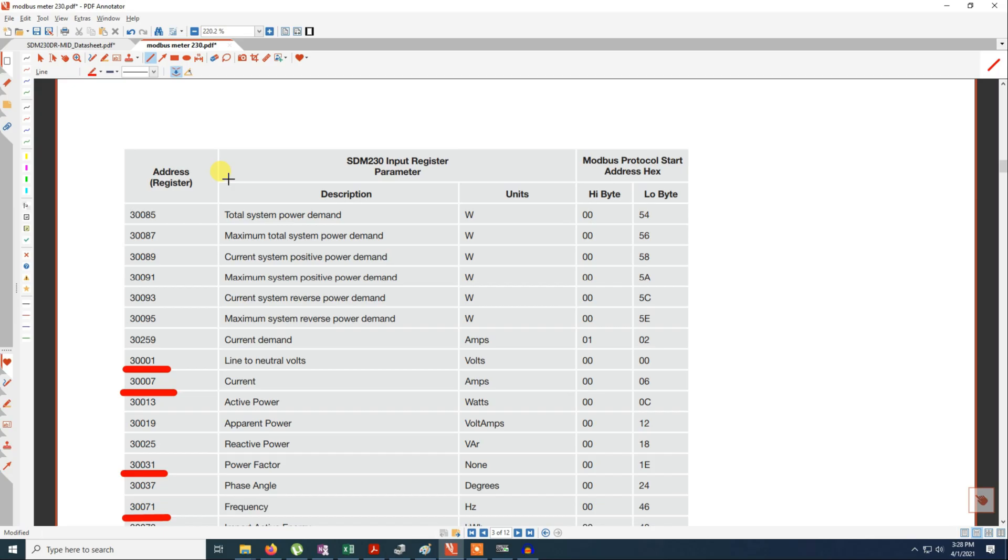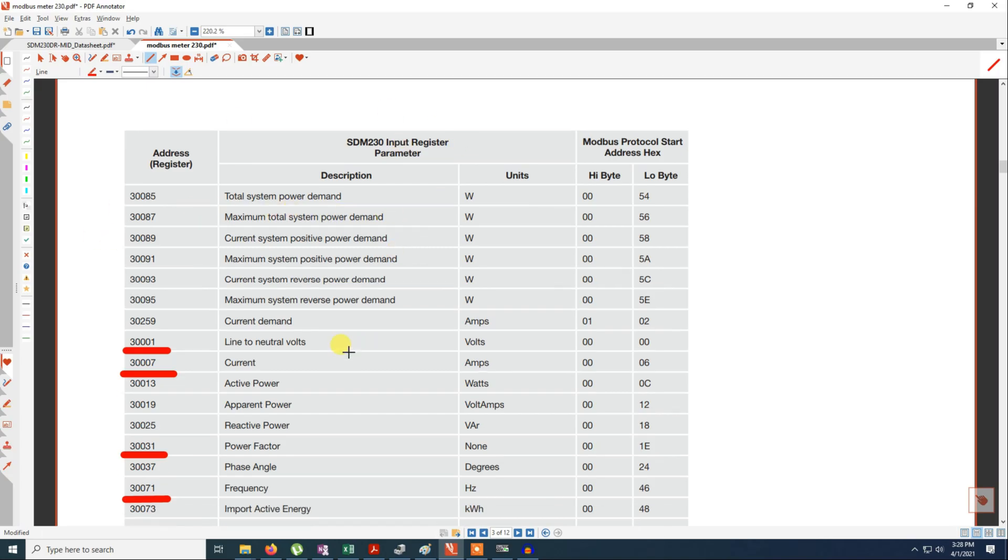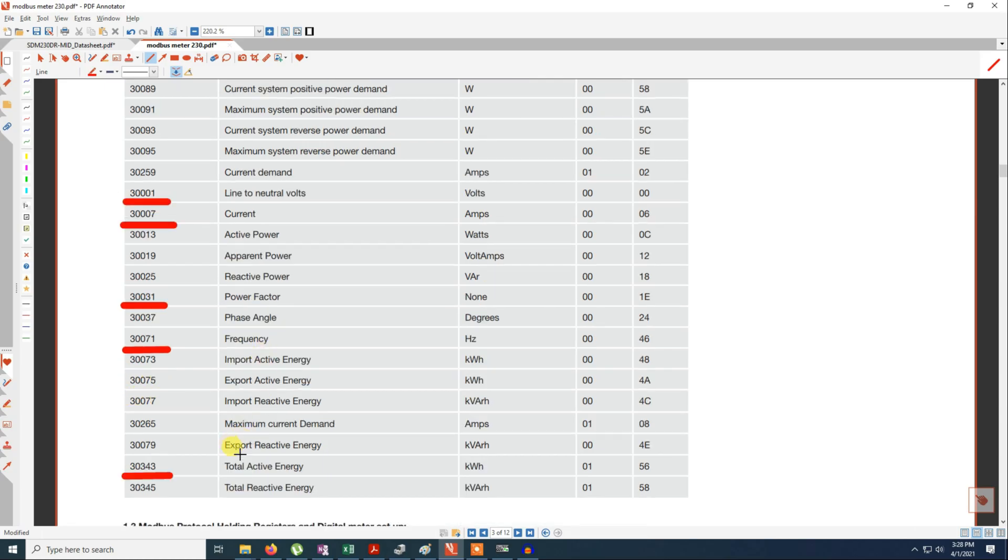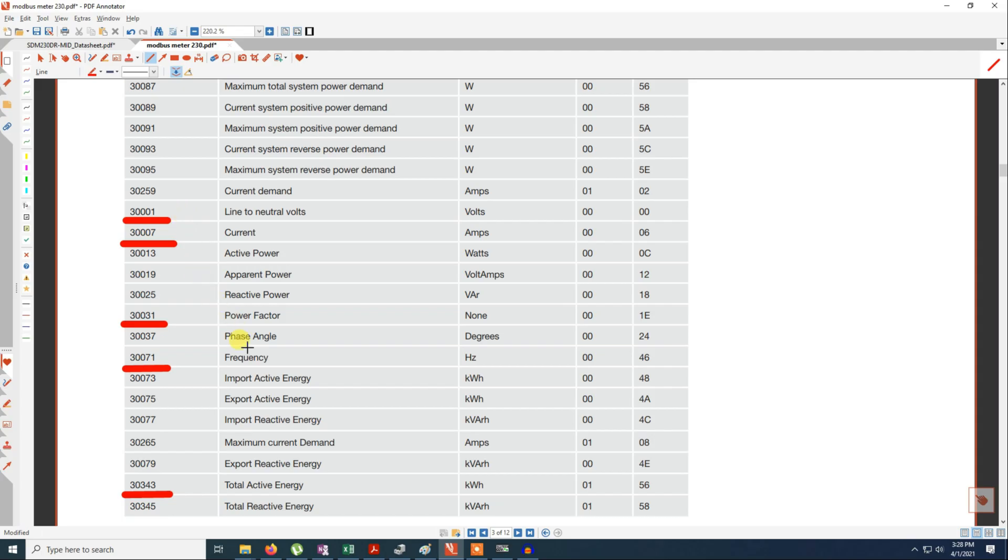For MODBUS, to read it you should refer to the MODBUS data sheet. For this meter this is the MODBUS registers. To know the voltage we should refer to 30001. For the current 30007. For the power factor you should go to register 30031. For the frequency you should go to 30071. And for the total accumulated kilowatt hour you should go to register 30343. Based on this register you will be able to read the various parameters such as amps, voltage, watts, the frequency.